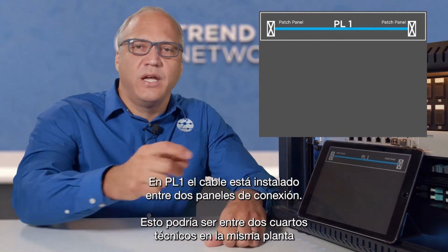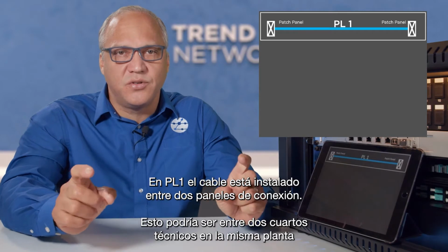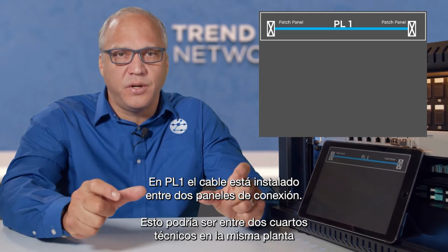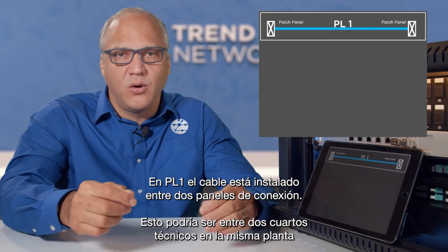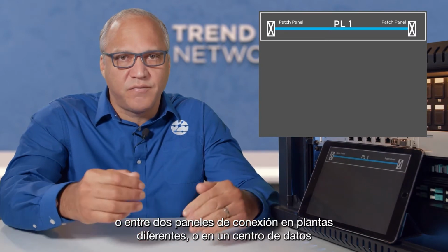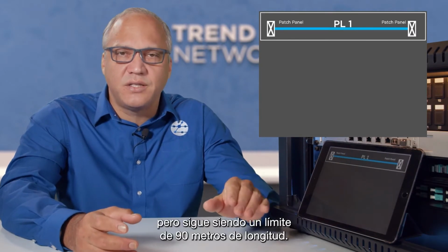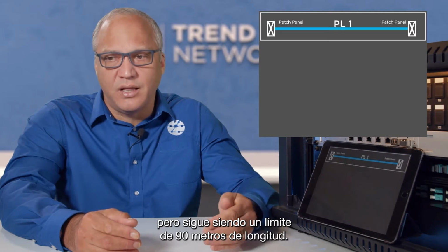So PL1 is where the cable is installed between two patch panels. This could be between two equipment rooms on the same floor, or between two patch panels on different floors or in a data center, but it's still a 90-meter length limit.